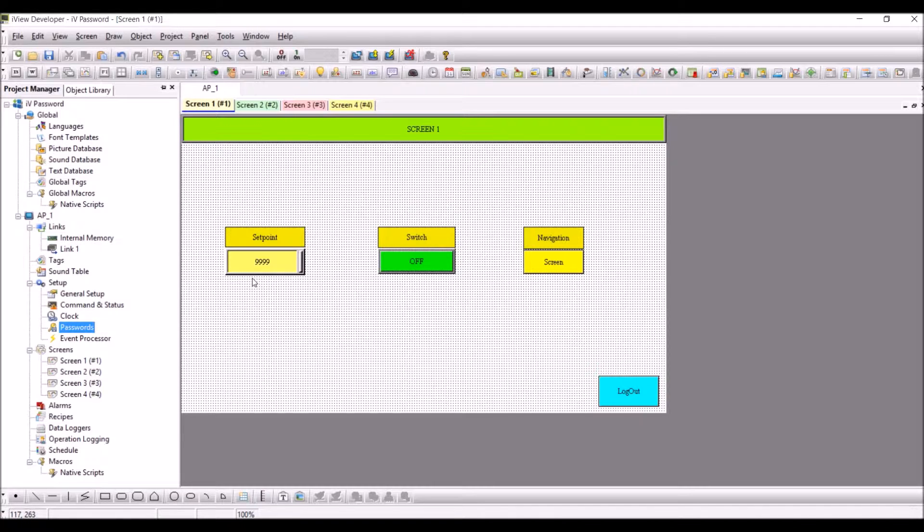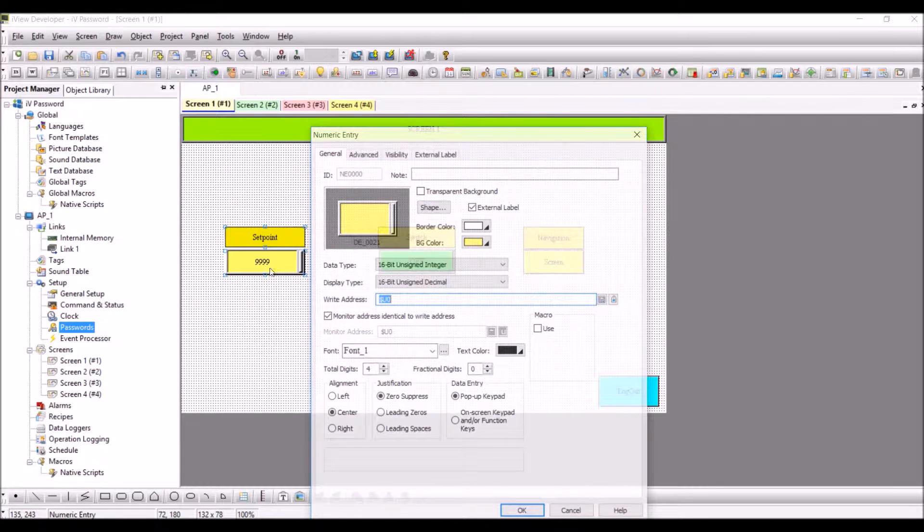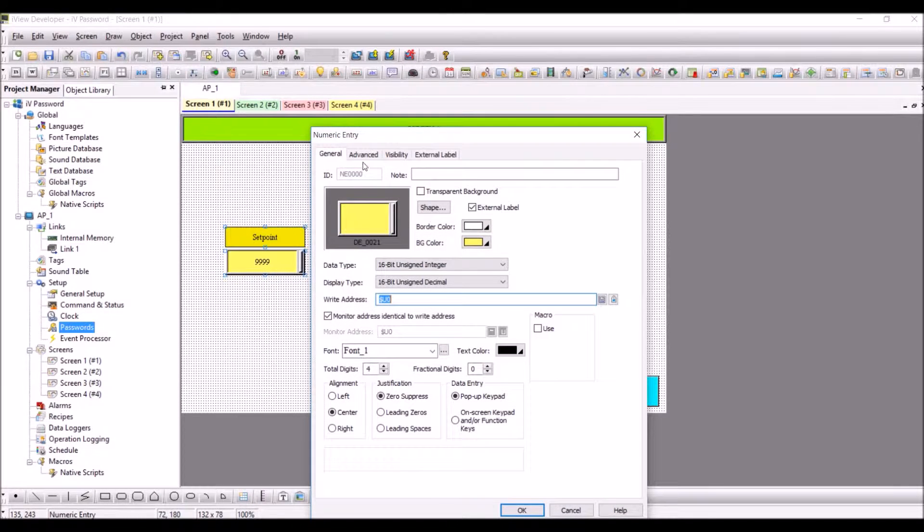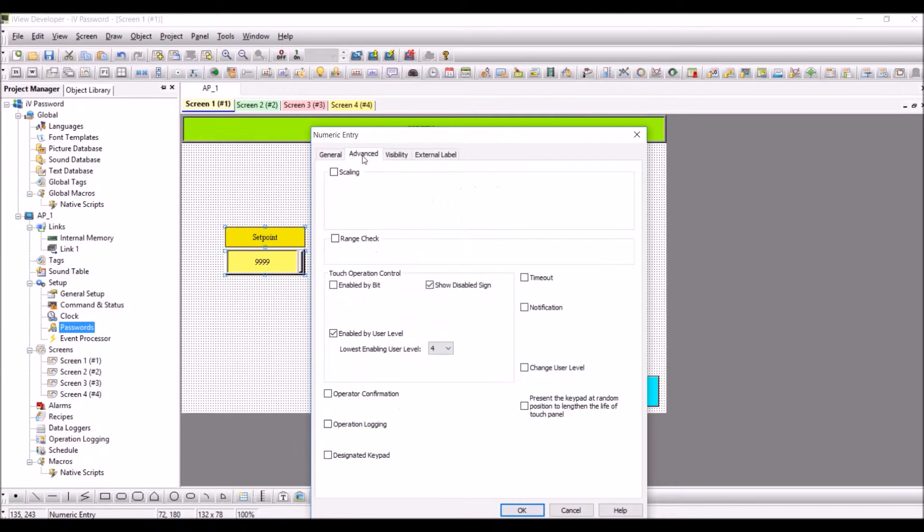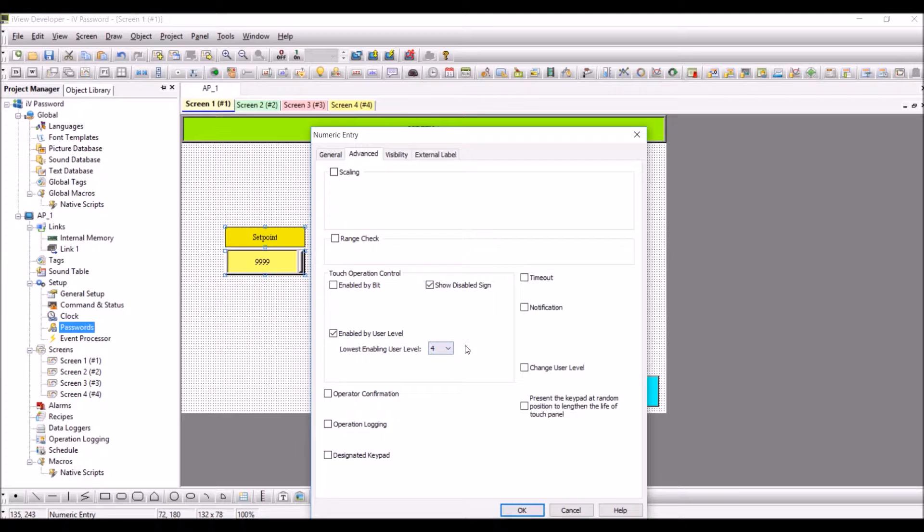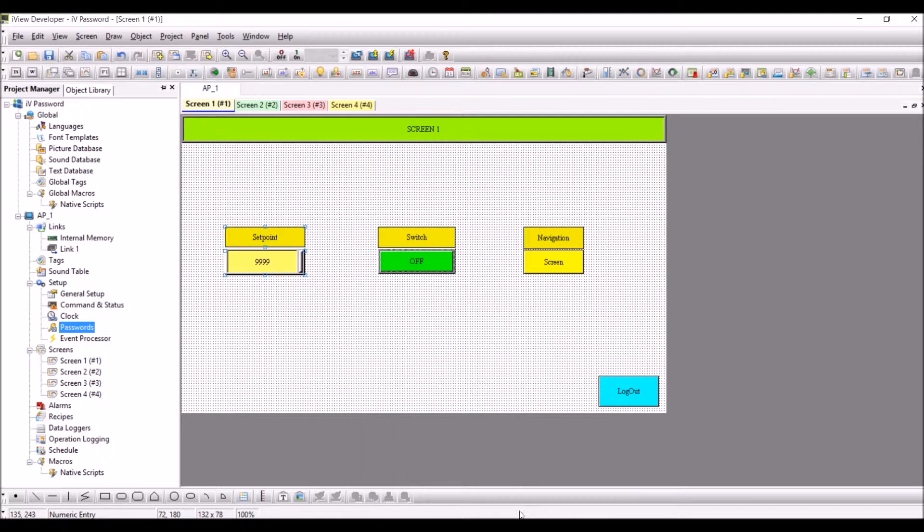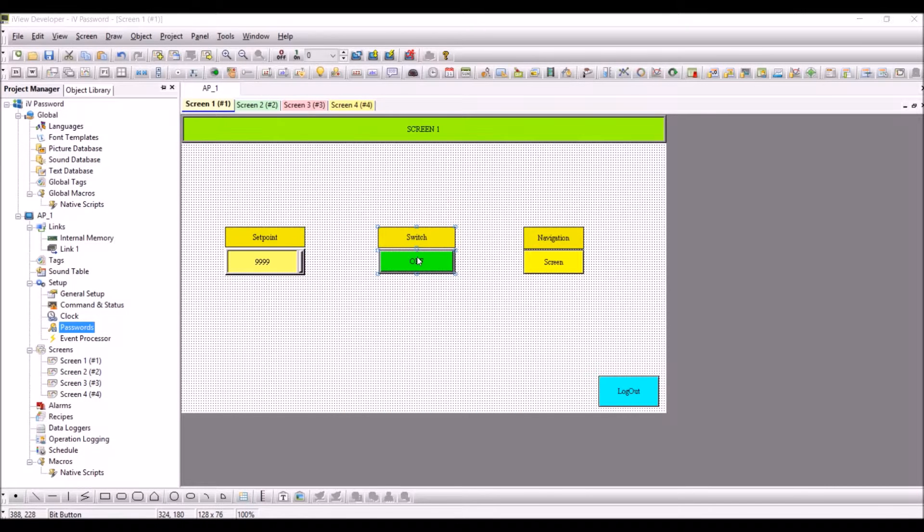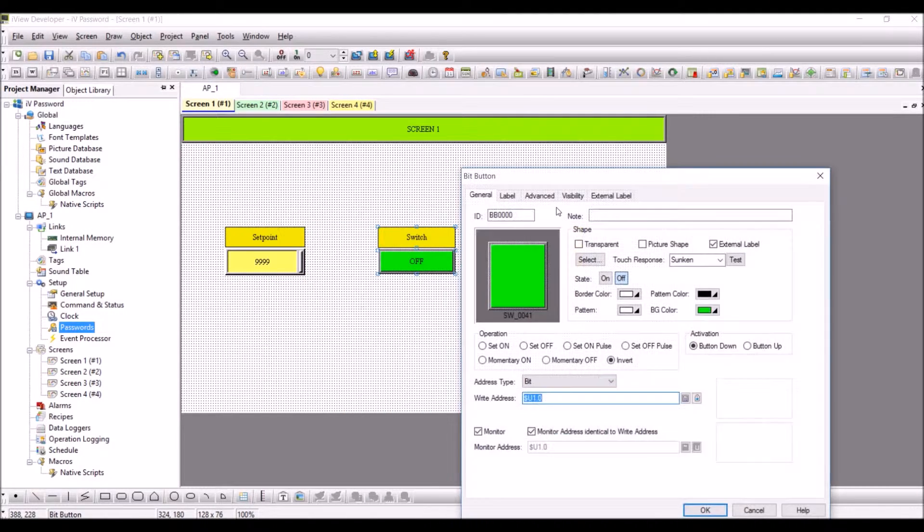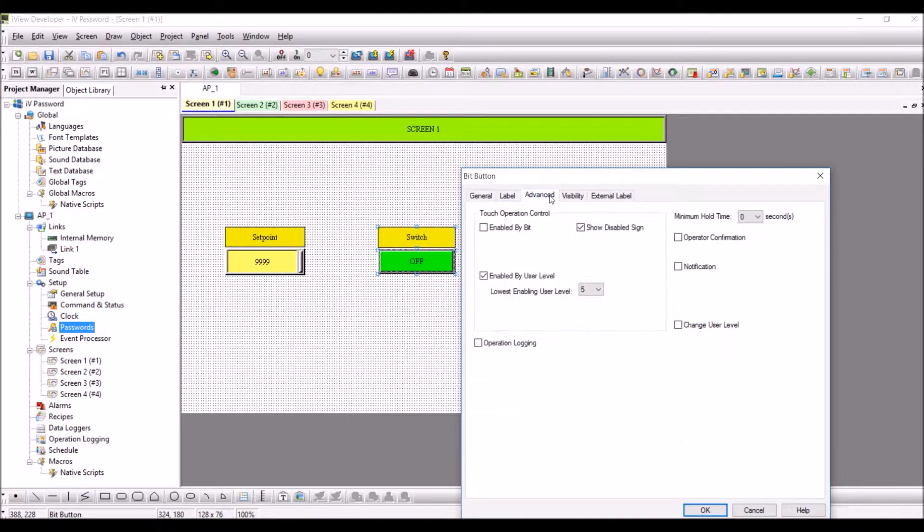Double-click on the setpoint, click on advanced. Here you have touch operation control. Check the checkbox for enabled by user level. Here you have lowest enable user level, and I have set it as four. Press OK.